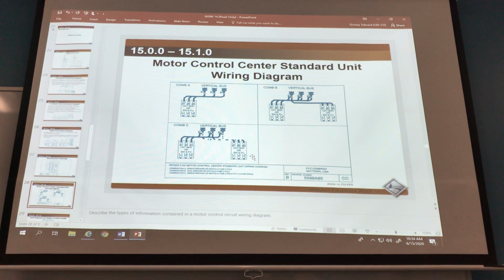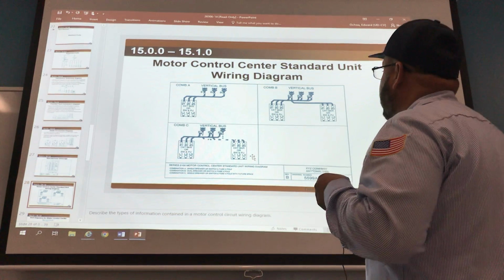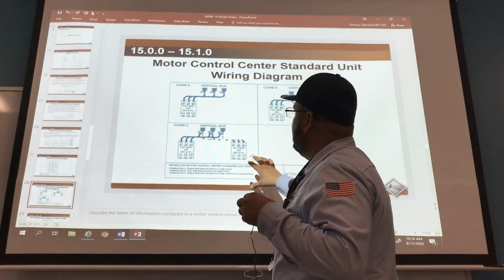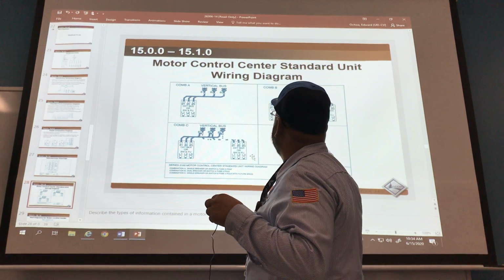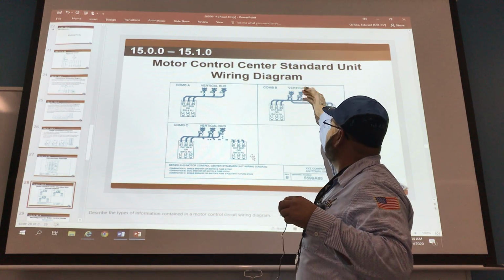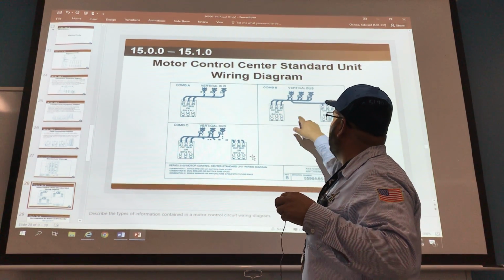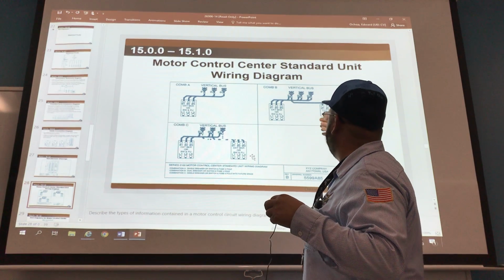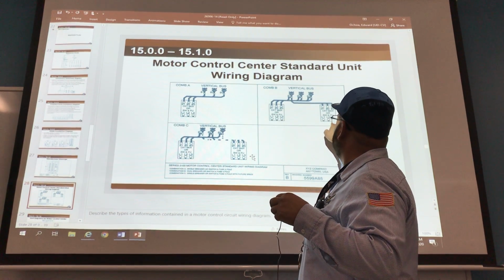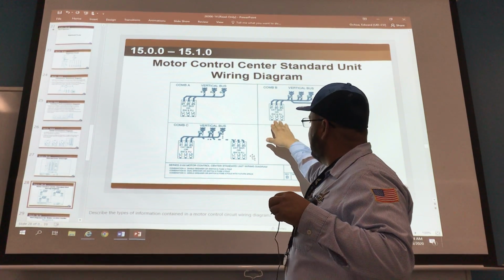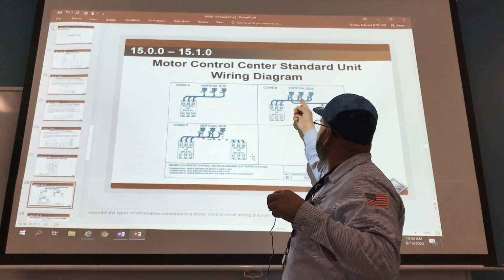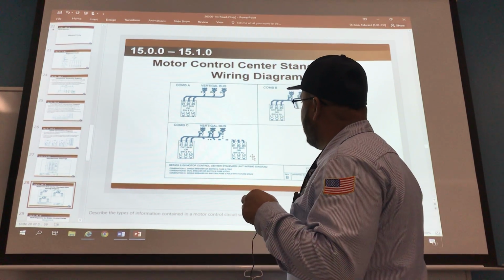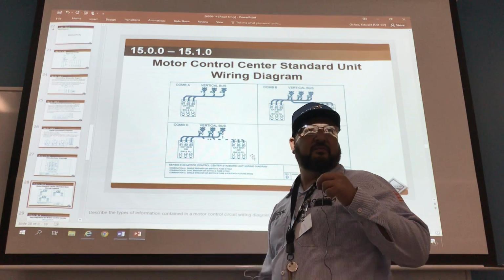Here's your motor control center stand units diagram. This shows you how it works. Look at, here's your vertical bus. This is power coming in, circuit breaker or switch, or fuse, same thing here. But you've got your L1s, L2s, L3s. Actually, this is your lines, that would be your loads, but I don't know why it's coming like that. But your line is always coming from the top.